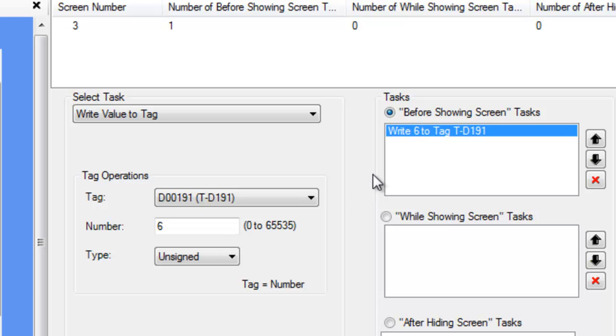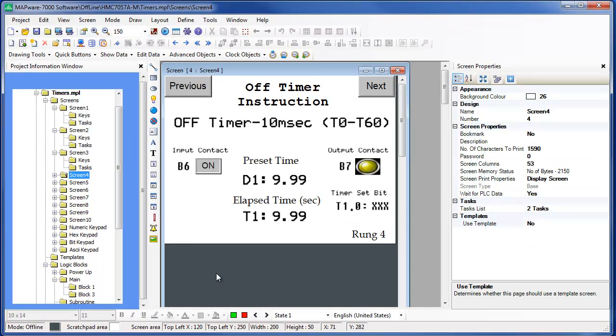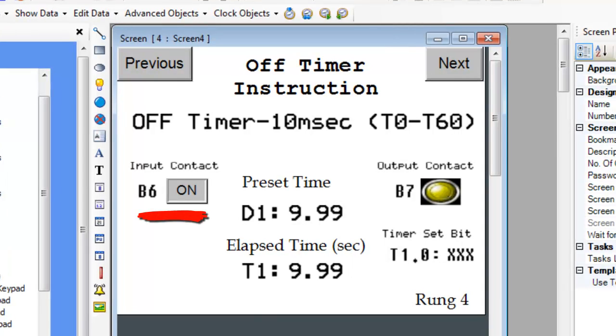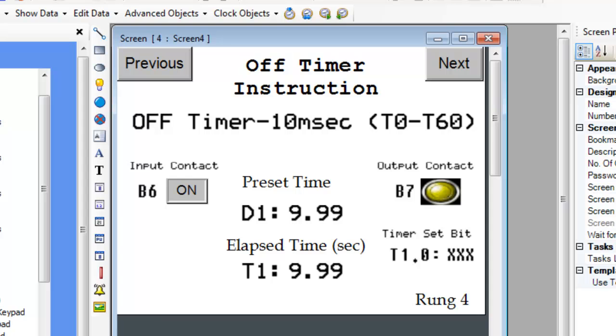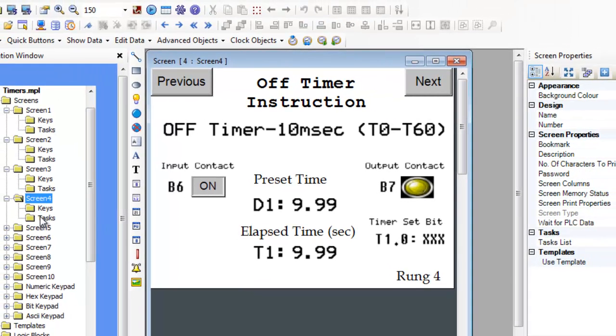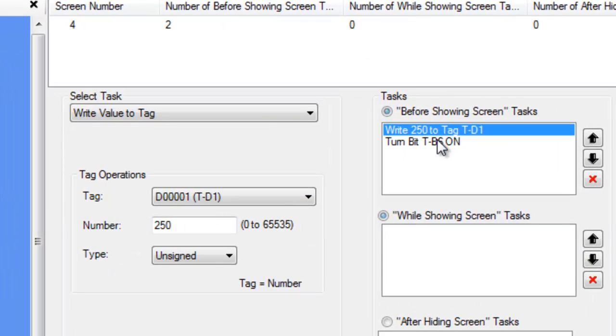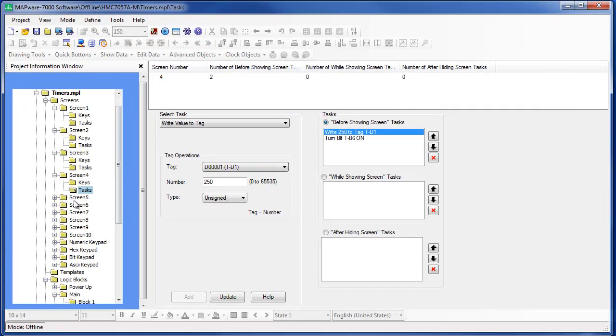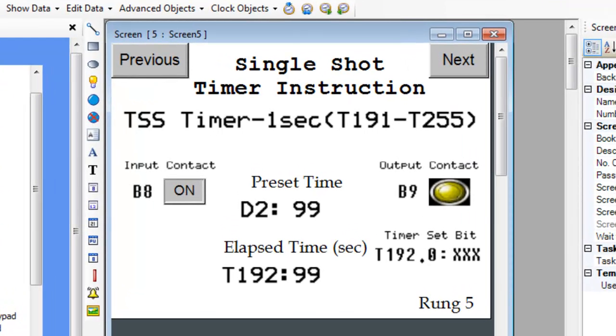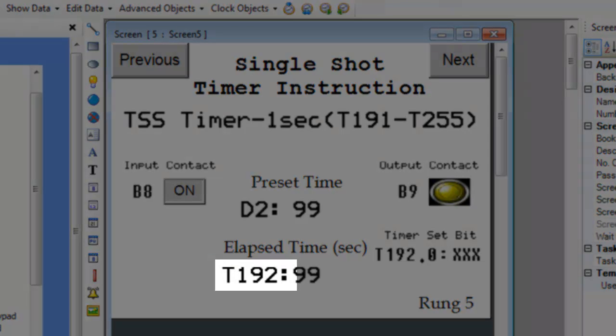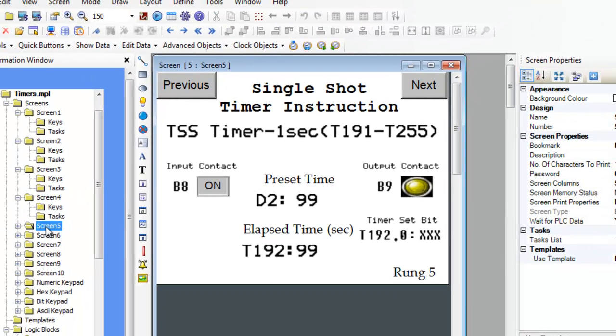For screen 4, we show an off timer configured for 10 millisecond intervals. Toggle bit B6 will activate this timer when it is in the off state. We want the B6 input contact to be normally on when we enter this screen. In the task folder, we have configured the preset register to 250 so that it will count for 2.5 seconds. Screen 5 demonstrates how the single shot timer works in rung 5. Since this timer does not require the input contact to remain on, we use a momentary contact for B8. Output B9 will turn on when counting begins and shut off when the count value in T192 reaches the preset value in D2. The task folder configures the single shot timer to count for 5 seconds.